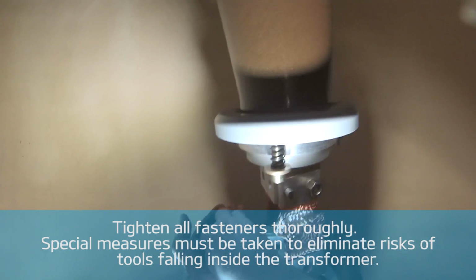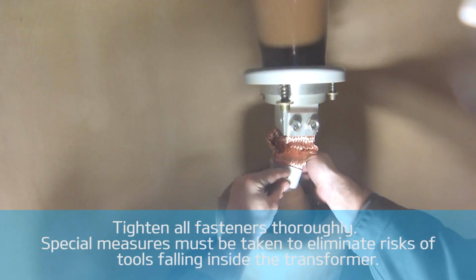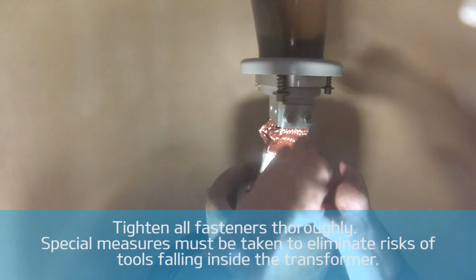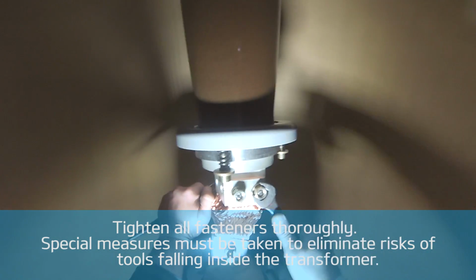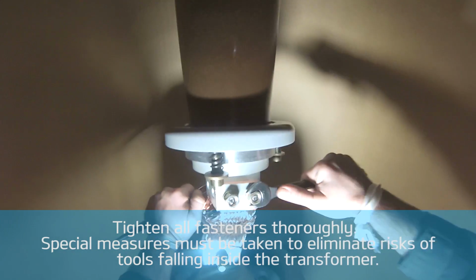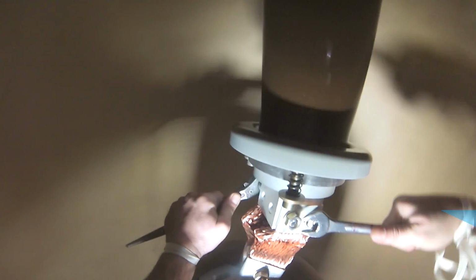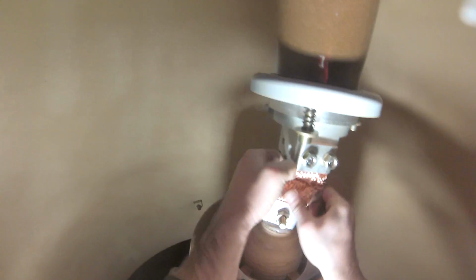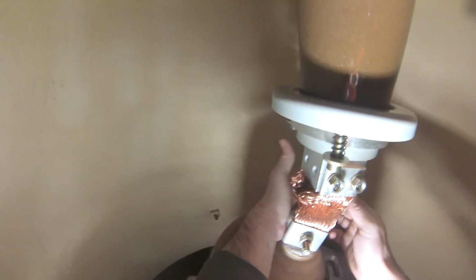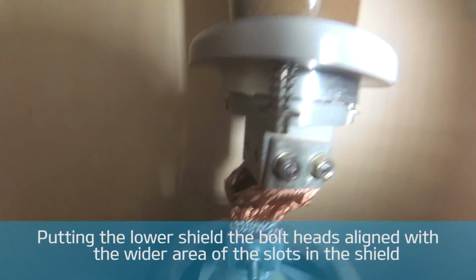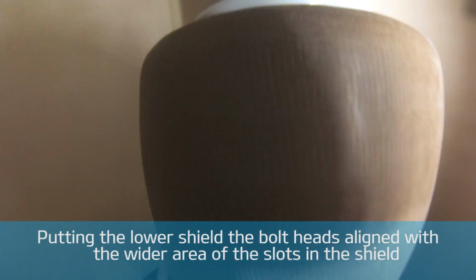Special measures must be taken to eliminate risks of tools falling inside the transformer. The simplest method is binding tools to your hand with a suitable material. After flexible connectors are installed, place the shield in its proper location by putting the lower shield on the contact tip so that the bolt heads align with the wider area of the slots in the shield.